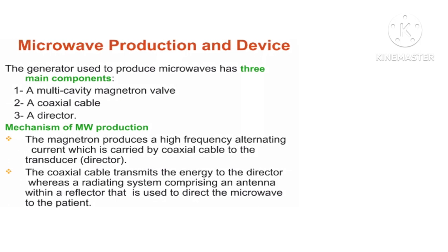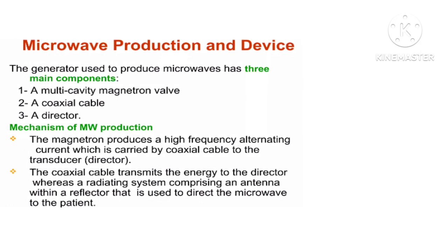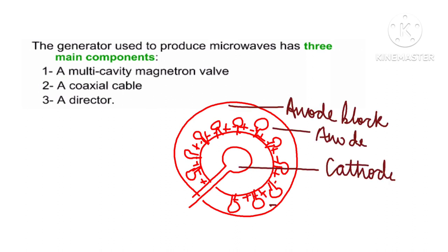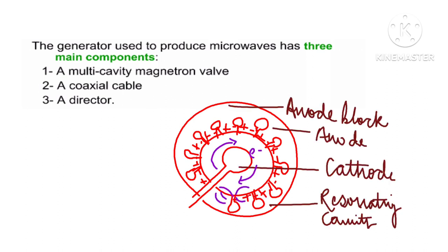Microwave diathermy also works on the principle of thermionic emission. Now let's look at the production of microwave radiation. To produce it, there are three basic components: first, a multi-cavity magnetron; second, a coaxial cable; and third, a transducer. In the magnetron, the cathode is present in the center, surrounded by the anode with anode blocks forming resonating cavities.